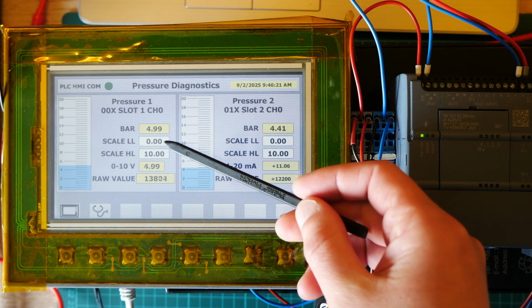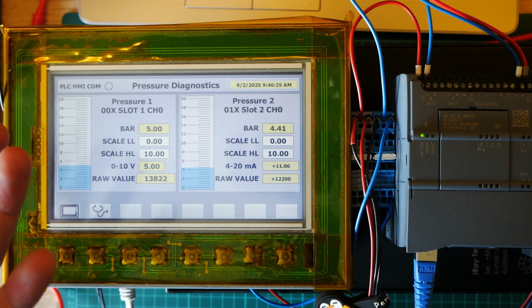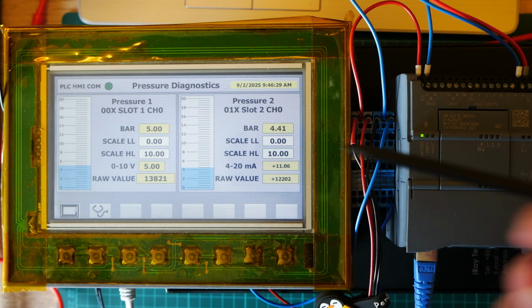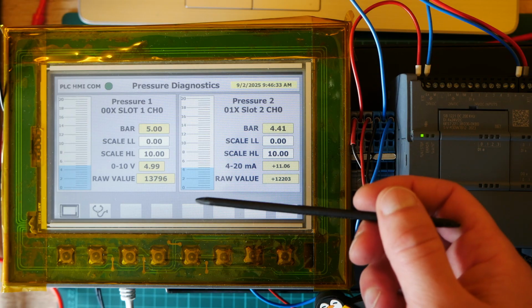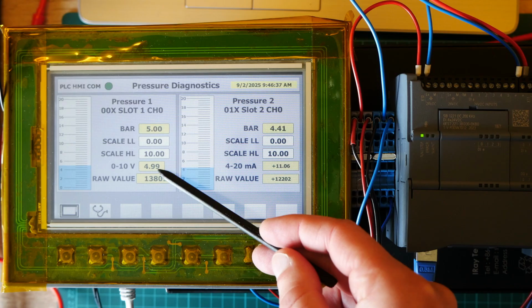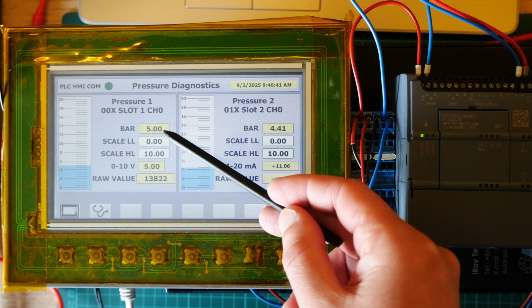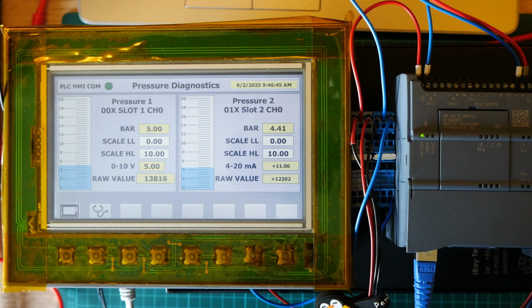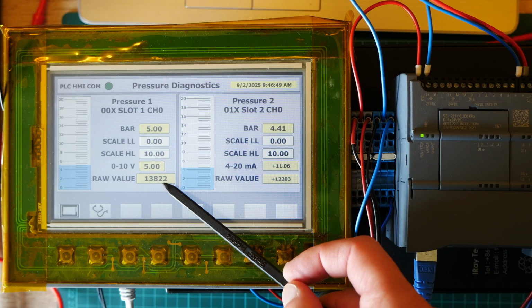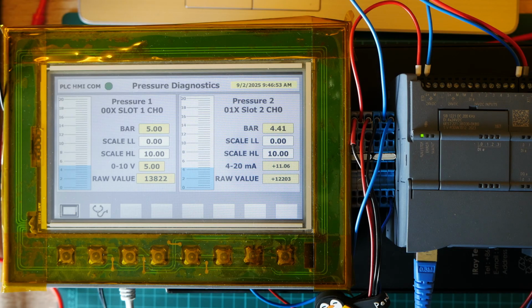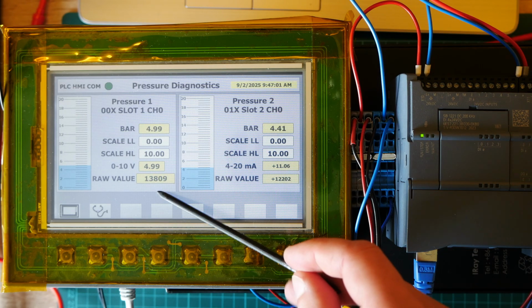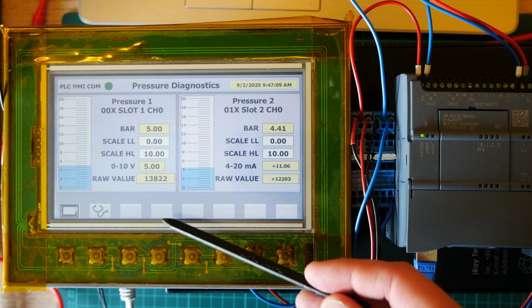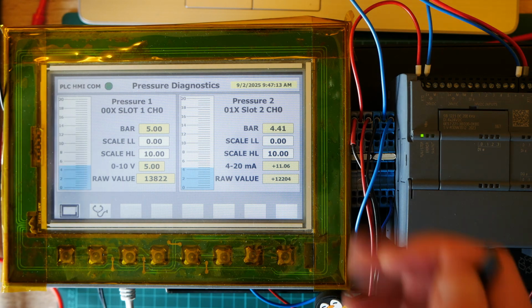So as you can see, our sensor scale is from 0 to 10 bars, and our analog input is also from 0 to 10 volts. So right now the PLC sees 5 volts, and after scaling we have 5 bars. So this is okay, this is working fine. This is the raw value just from the sensor itself. It's not scaled, it's just the raw value. In the HMI I set the acquisition time to refresh this value every 100 milliseconds, so it's refreshing quite fast.